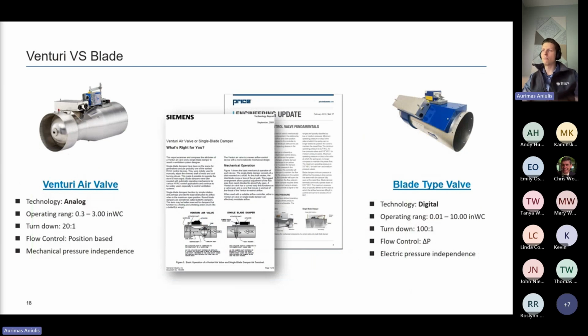When it comes to industry preference, there are really two camps of specifications that I see. One is a Venturi-based design, and the other is a blade type based design. There is a lot of debate in this field, and this is purely my opinion, but there's a place for both of these in the industry. Venturi air valves are great for fume hood exhaust. They have no sensors in the airstream, as we will talk about.